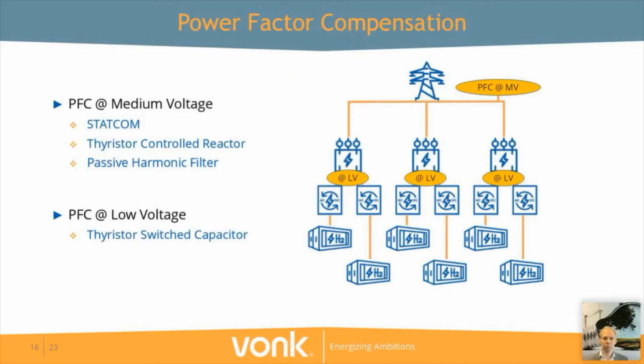The other option is to apply power factor compensation at low voltage. And this is actually the option that we prefer when possible. There are three main advantages when applying power factor compensation at low voltage level. The first one is that you can integrate it in the building blocks of your power supply. I will come back to that later. The second one is that it requires less floor space overall, so combining all decentralized power factor compensation units together when compared to power factor compensation at medium voltage level. The third one is quite simple, and that is that it's cheaper.